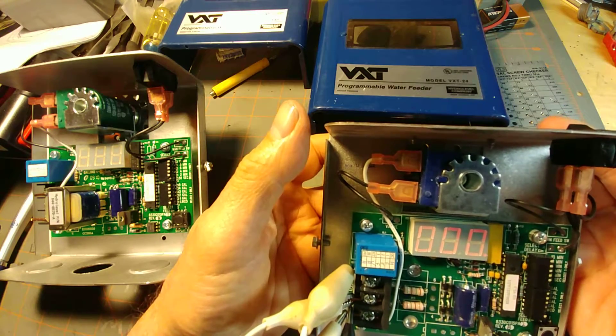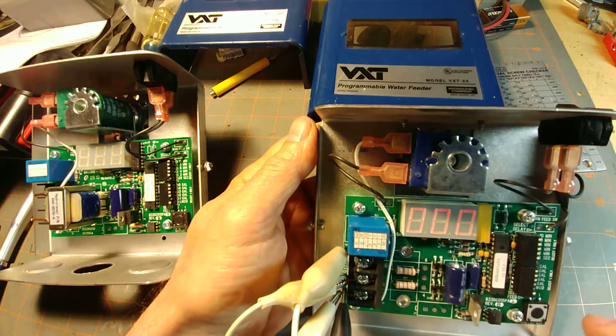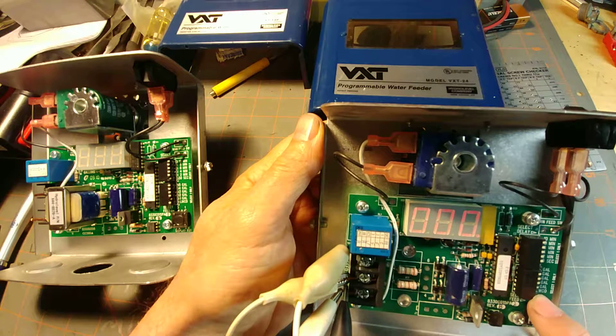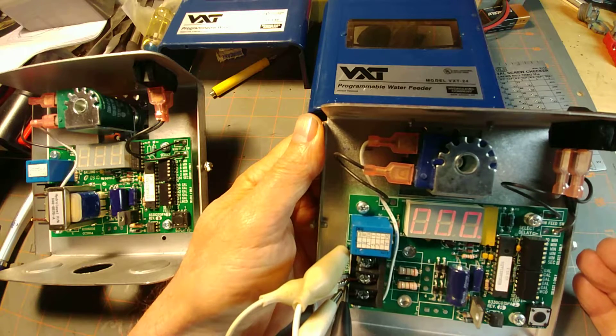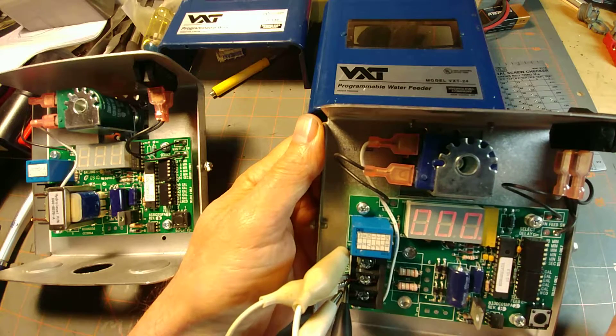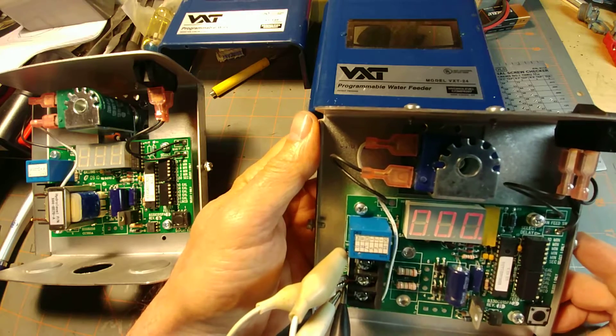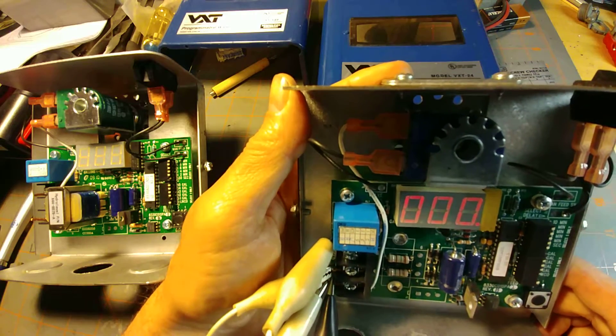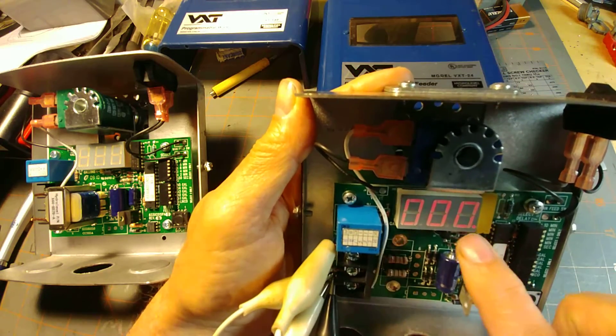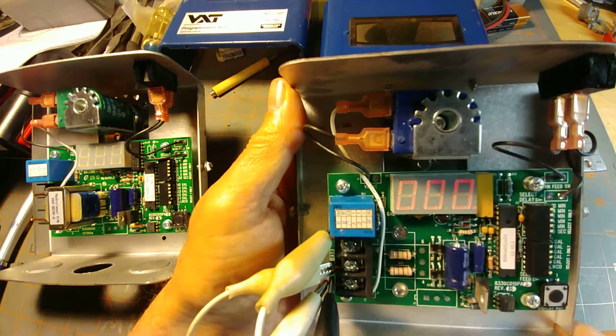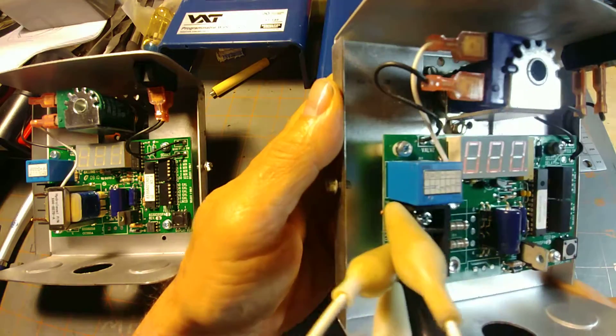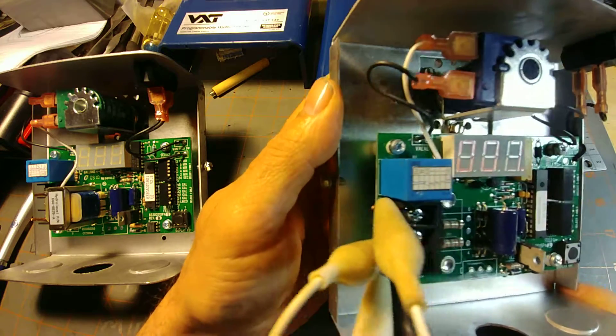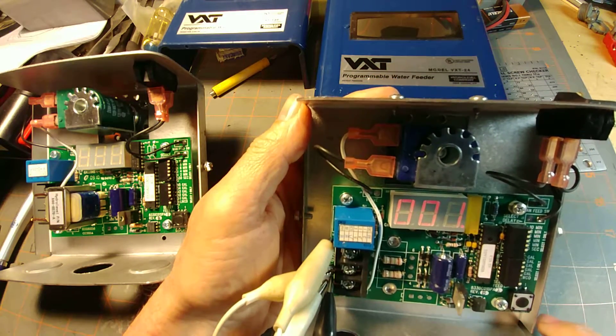If you've got this thing plumbed properly, water is going to flow through the solenoid valve and into the boiler. Since we've set it at one gallon per cycle, the solenoid is going to stay open for a set period of time, which is more or less equivalent to one gallon. Eventually, this is going to go from zero to one, and pretty soon it's going to stop.